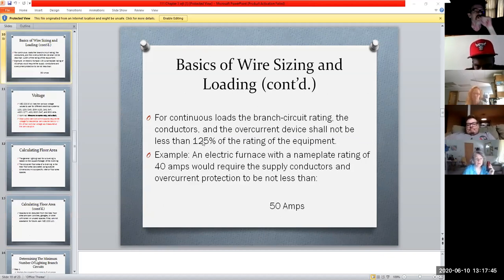So when you have that, we have a little multiplier right here where we say, oh, well, then it's 125% of that. So how's our example? We have an electric furnace, and on the nameplate on that furnace, it says it would need a 40 amp breaker, a 40 amp circuit. If that's the case, then we multiply that 40 amps by 125%, and we come up with 50 amps. So if we put a 40 amp breaker in for this furnace, it's going to trip all the time, because after a while it's just that current buildup and it's going to exceed the rating, right? It's going to be tripping because that's continuous duty. So you can see that by multiplying out with this 125%.